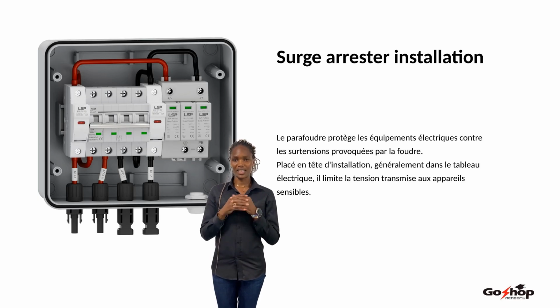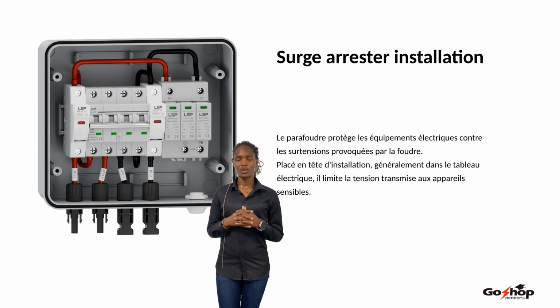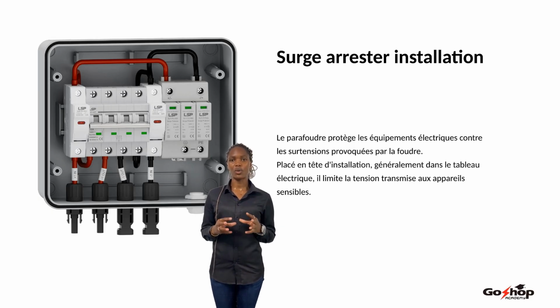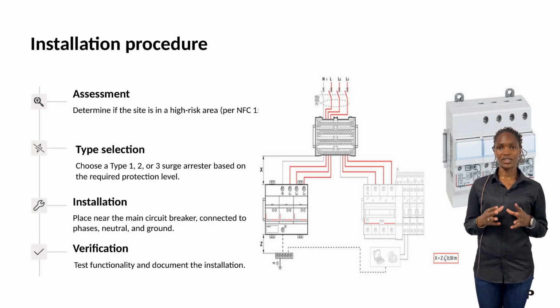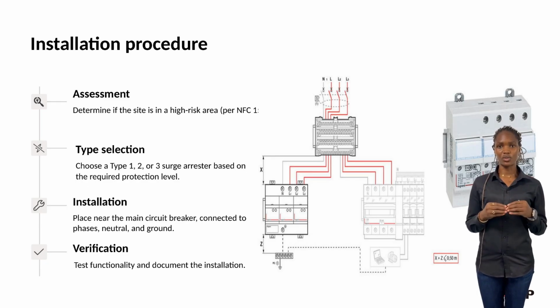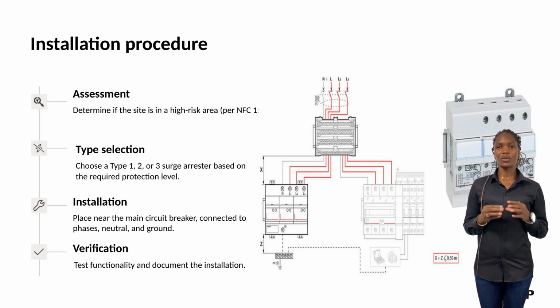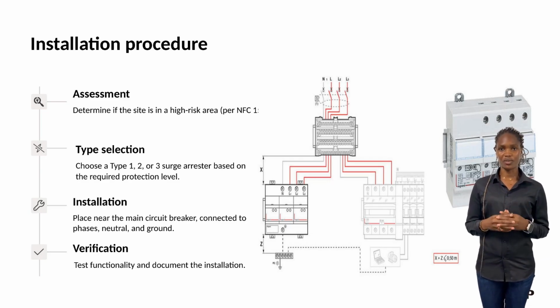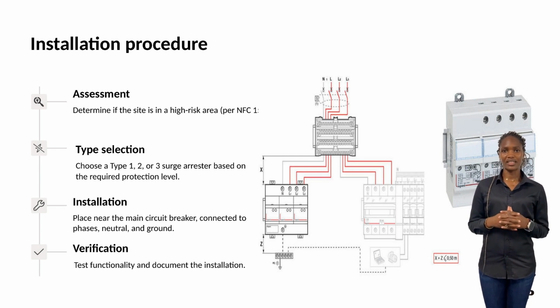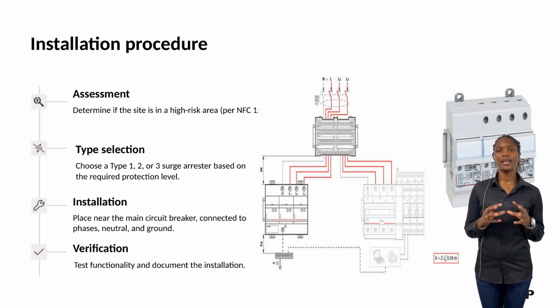The surge arrestor protects electrical equipment from overvoltages caused by lightning. It is installed at the top of the electrical system, often in the distribution board, and limits the voltage that reaches sensitive devices. To install a surge arrestor, first, check whether the site is in a high-risk zone according to NFC 15-100. Then select a Type 1, 2, or 3 surge arrestor based on the required protection level. Install it near the main circuit breaker and connect it to the phases, neutral and ground. Finally, test its function and document the installation.